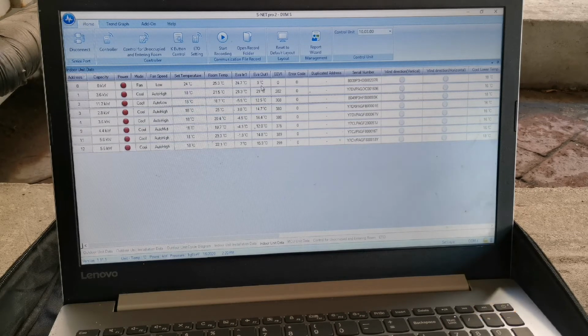The recommendation was that we run the system like this for about 10 to 15 minutes, and once we waited for that period, we will then reinstate this unit that's on fan only and put it on cooling and see how that changes the sensor values, because that could be causing our electronic expansion valve to be acting erratically. I mean, you can see the temperature difference between in and out. There's about a 13 degree difference, and our expansion valve is completely closed. So that's interesting.